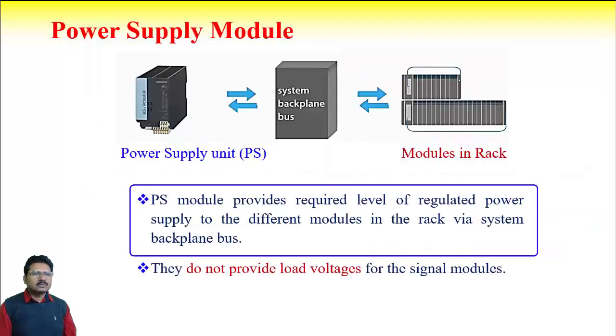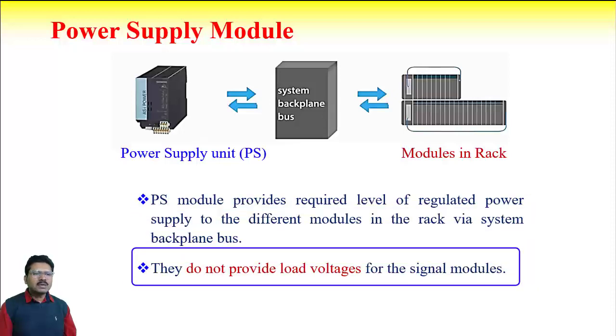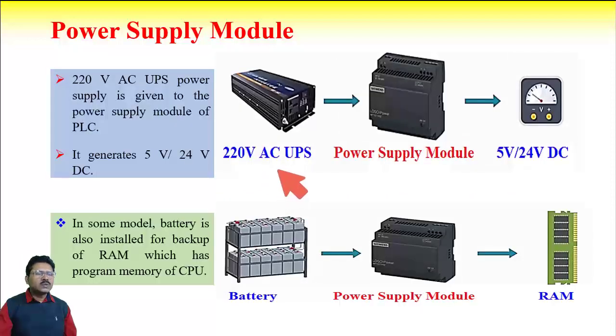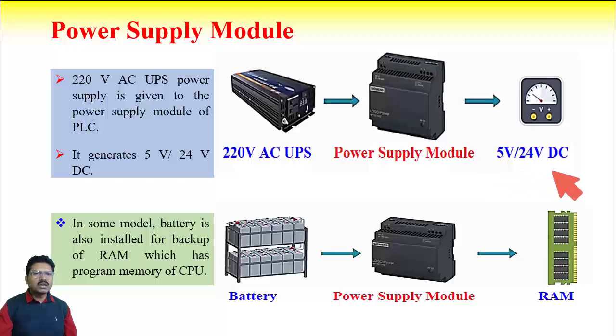The power supply module provides the required level of regulated power supply to the different modules in the rack via the system backplane bus. The power supply module does not provide load voltage for the signal module. In general, 220 volt AC UPS power supply is given to the power supply module of the PLC, and this module ultimately generates 5 or 24 volt DC which is normally required for the different modules. In some modules, a battery is also installed for backup of RAM which holds program memory for the CPU.